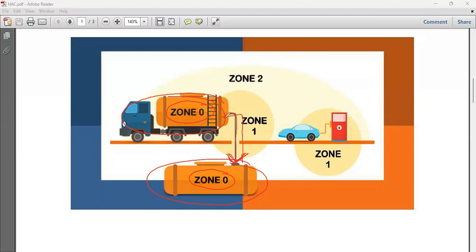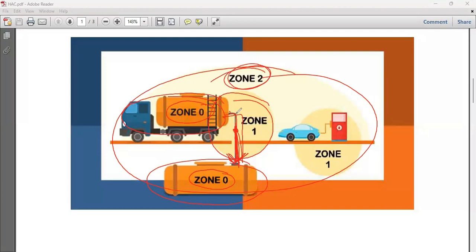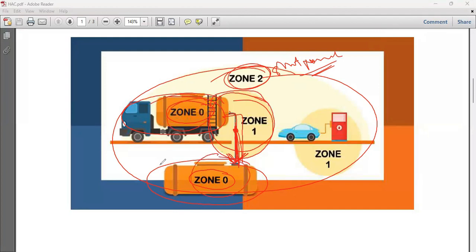When normal operations happen around the tank — such as opening and closing valves — that area is known as Zone 1. The wider surrounding area is Zone 2, where the hazard exists only for a short period of time. So Zone 2 contains Zone 1, and inside Zone 1 is Zone 0, where the hazardous atmosphere is continuously present.